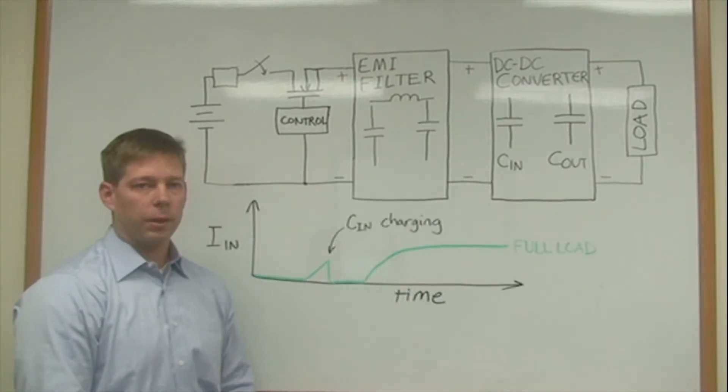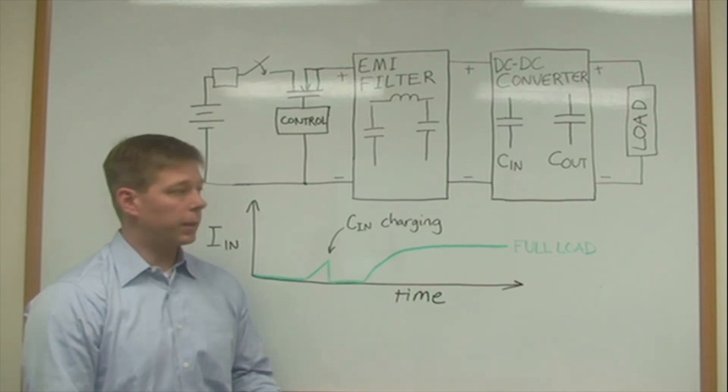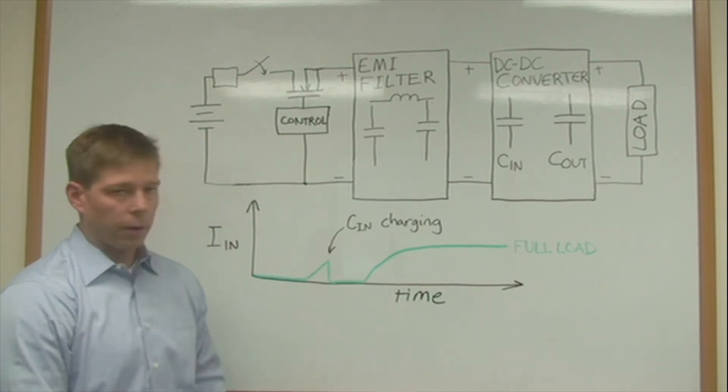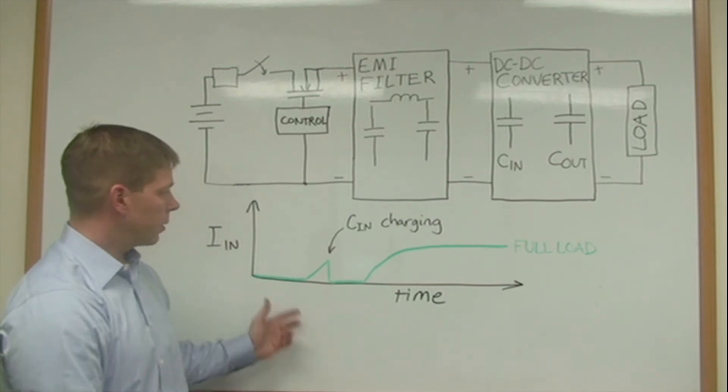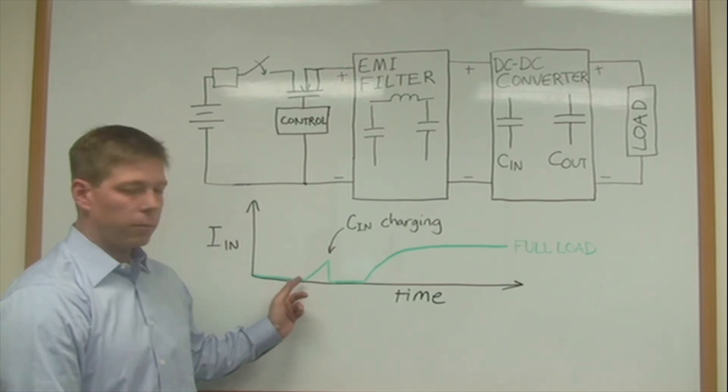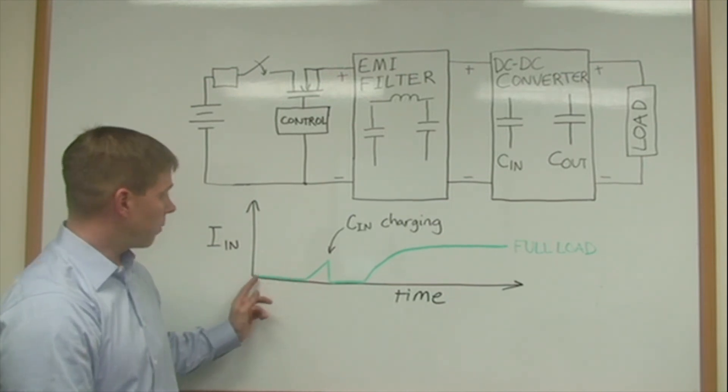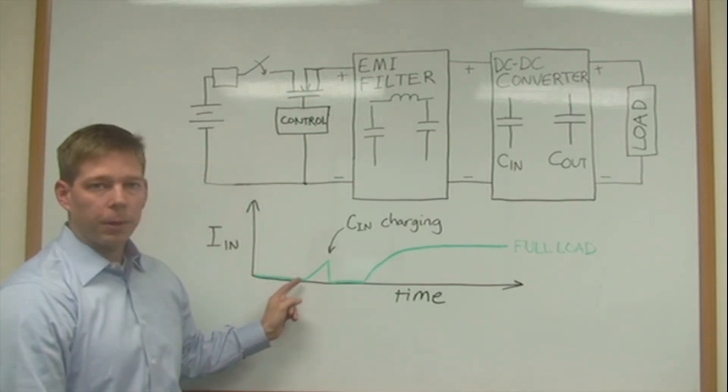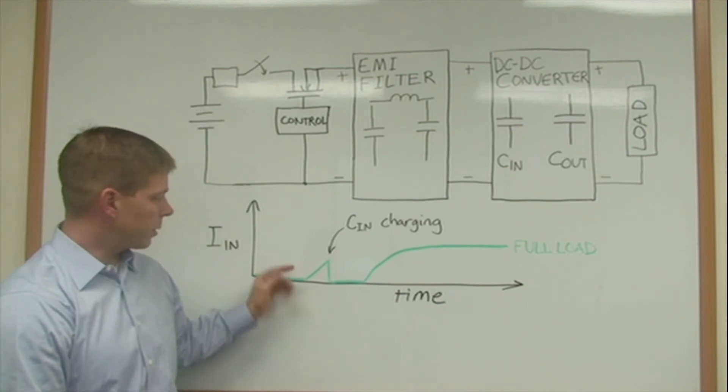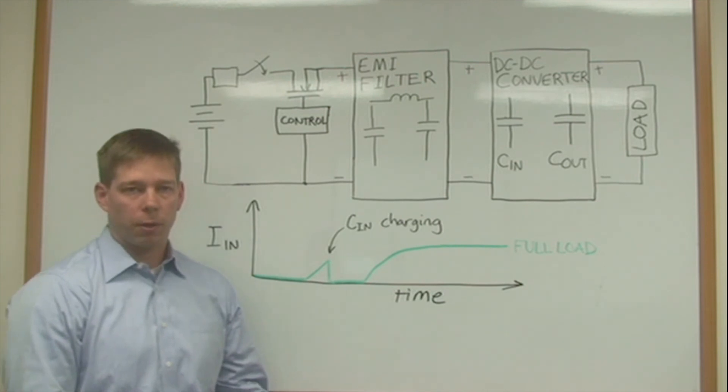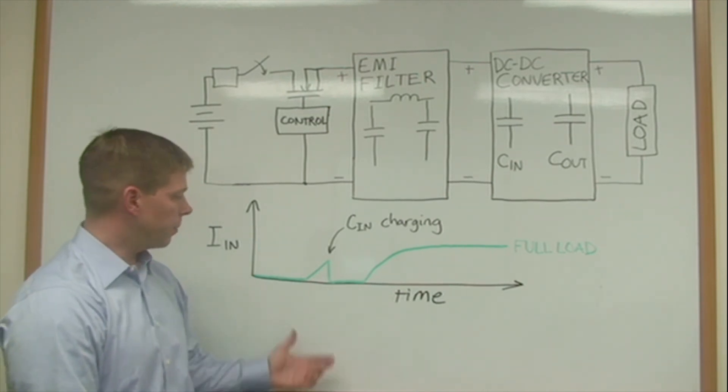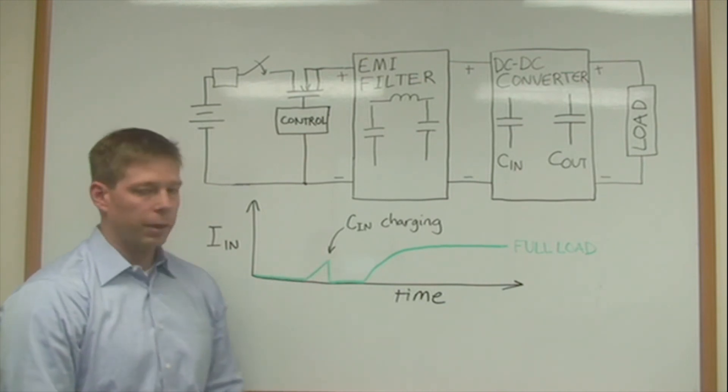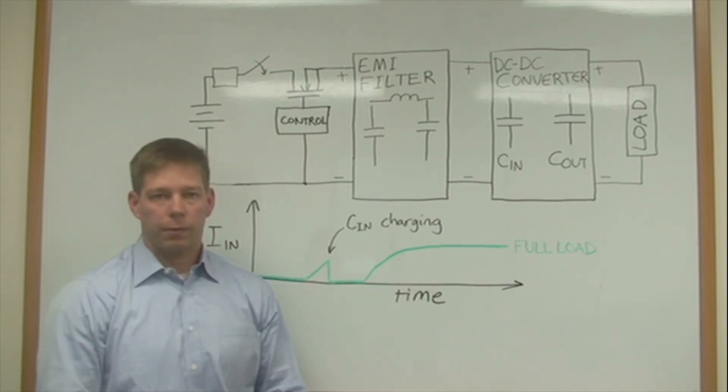With the inrush current limiting circuit implemented or with one of our products that control inrush current, your input current waveform is going to look like this. When the input switch is shut, the input capacitor charging waveform is going to be greatly reduced and the dI/dt of that waveform is going to be much lower. That will improve EMI performance and also the peak of that current never exceeds the full load running current of the converter.